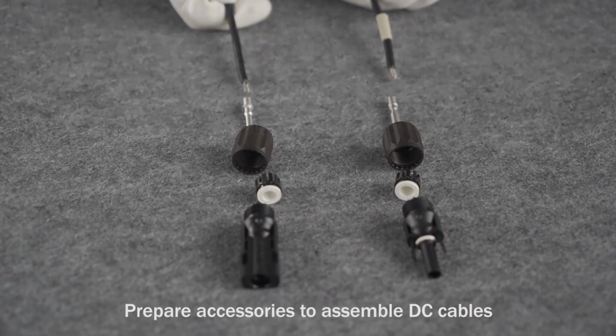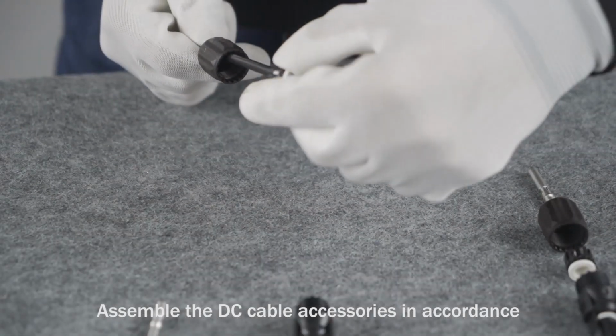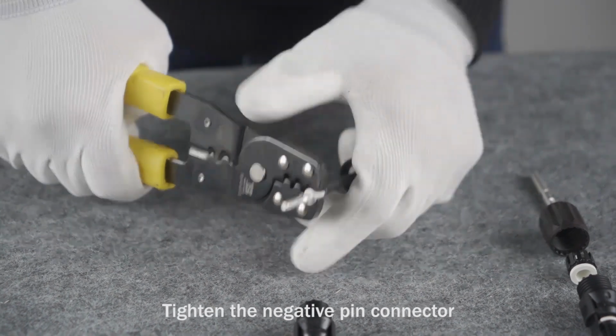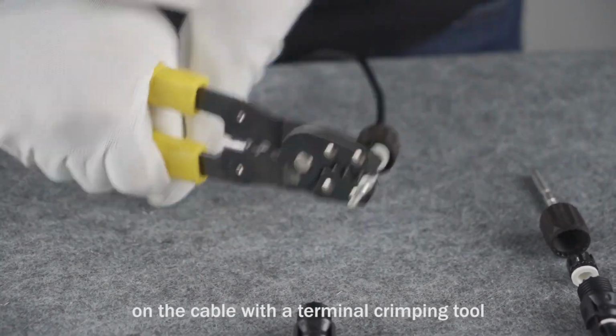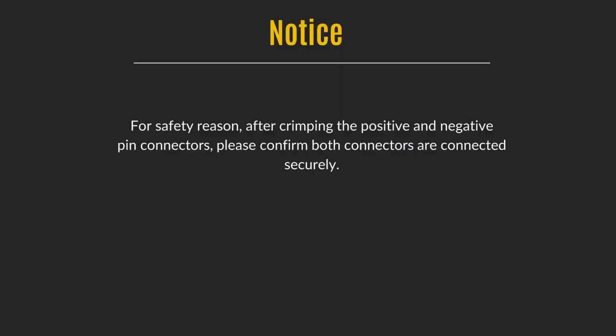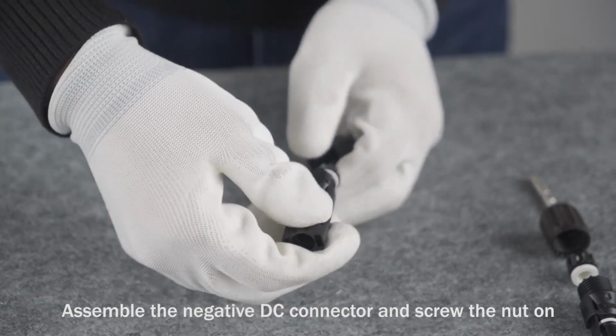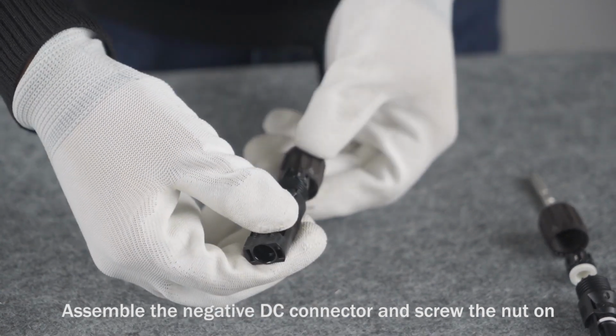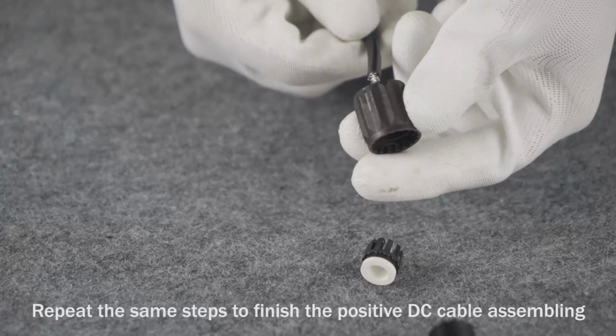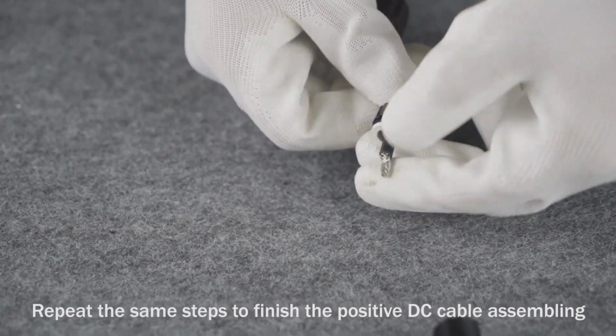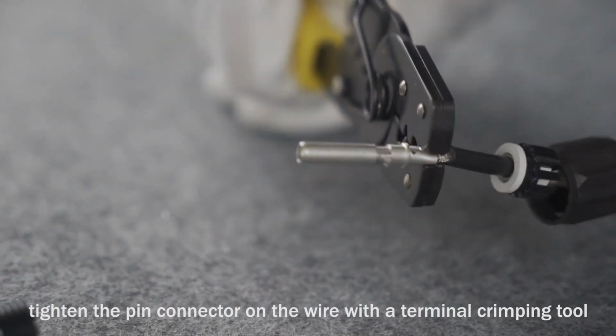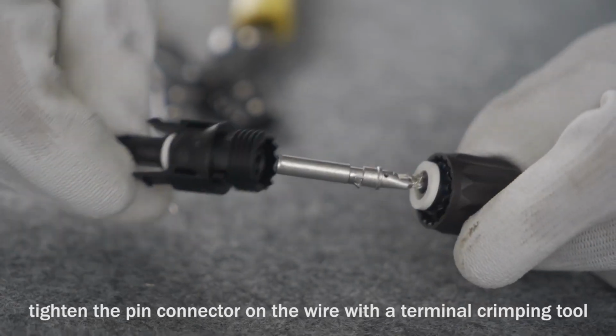Prepare accessories to assemble DC cables. Assemble the DC cable accessories in accordance. Tighten the negative pin connector on the cable with a terminal crimping tool. Assemble the negative DC connector and screw the nut on. Repeat the same steps to finish the positive DC cable assembling. Tighten the pin connector on the wire with a terminal crimping tool.